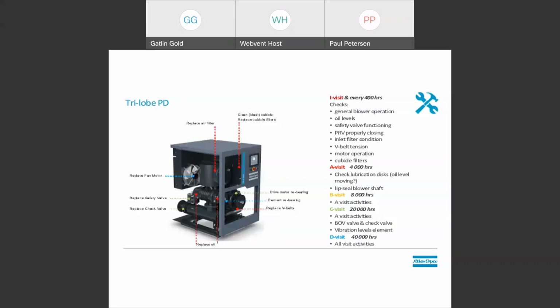So starting with the Trilobe positive displacement unit. Most blowers will have a short break-in cycle, which requires maintenance between 400 and 500 hours. This is mostly just to ensure that everything is working properly beyond the original commissioning of the units. Lobe blowers specifically require the most maintenance of any type of equipment. Typically, we can see things like motor greasing, oil changes, and belts to maintain efficiencies at 3 to 6 month intervals, depending on environmental conditions. If you have electronics on board, like VFDs or controls, we would also suggest cleaning electrical cubicles and checking connections, just to make sure vibrations haven't caused and can't cause shorts to occur.